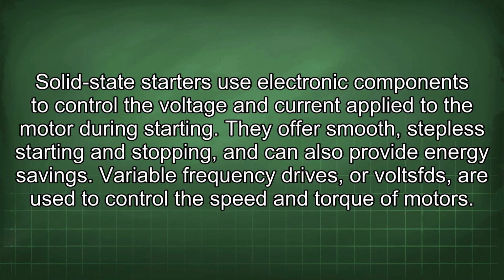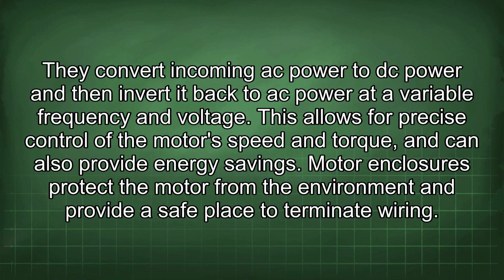Variable frequency drives, or VFDs, are used to control the speed and torque of motors. They convert incoming AC power to DC power and then invert it back to AC power at a variable frequency and voltage. This allows for precise control of the motor's speed and torque, and can also provide energy savings.